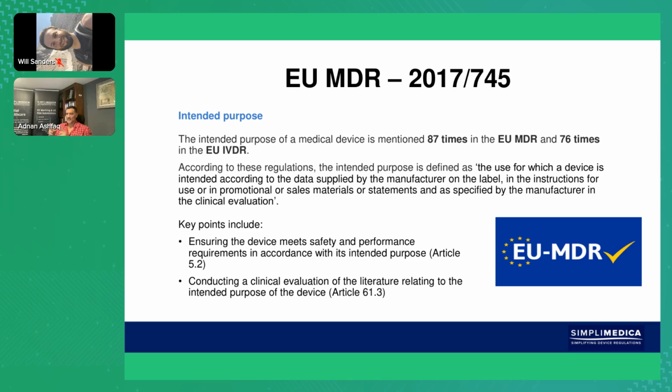Now you'll see there's similarities between what the US FDA had, but here they've also mentioned what's specified by the manufacturer in the clinical evaluation, because in the clinical evaluation we will make claims which are also based on the intended use, and we have to back that up with evidence. So the key points here are ensuring that the device meets safety and performance requirements in accordance with its intended purpose, and also conducting a clinical evaluation of any literature, which also has to be related to the intended purpose of the device.